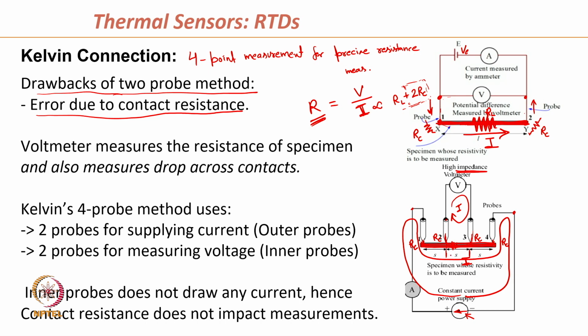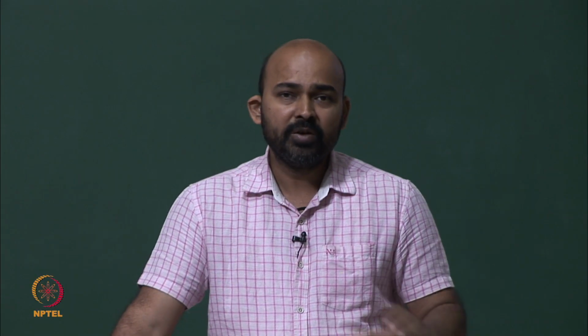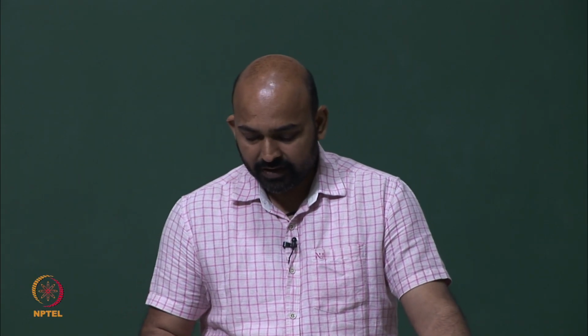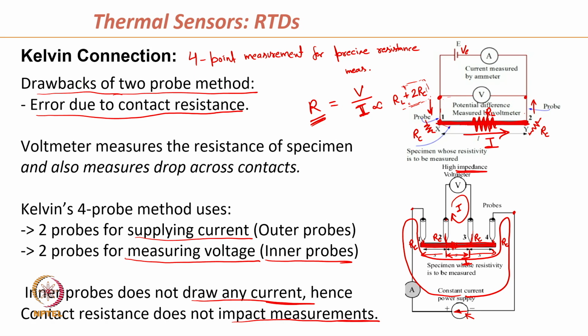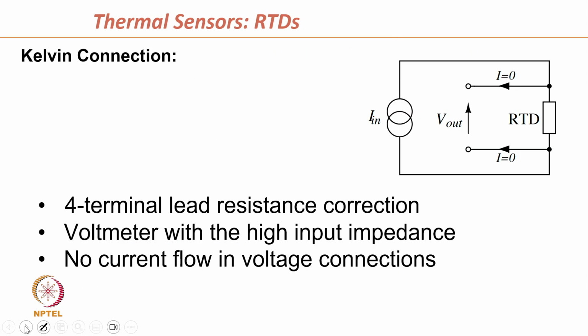So, between these 2 probes we are actually measuring the resistance, which we can again scale to the full length of this resistance value. So, this is the 4-point or the 4-probe method, which is also called Kelvin resistance measurement. We have 2 probes for supplying current and again 2 probes for measuring the voltage, which we call the inner probes. These inner probes do not draw any current, hence the contact resistance does not impact measurements. So, this RC is always there, contact resistance between 2 metals is always there, but the current is not flowing, so it does not impact the voltage reading.